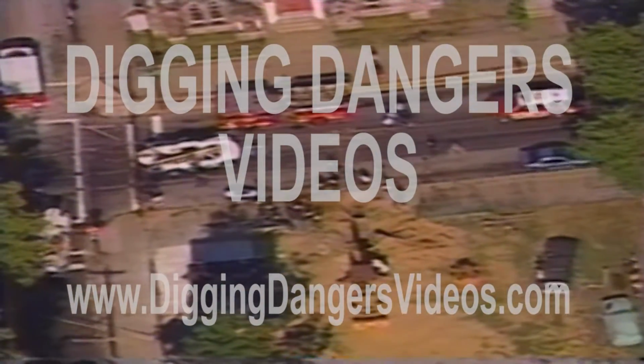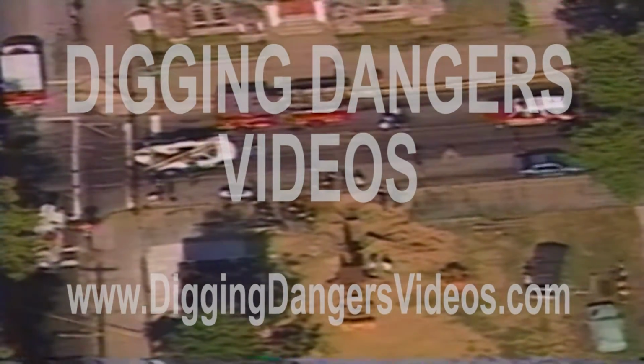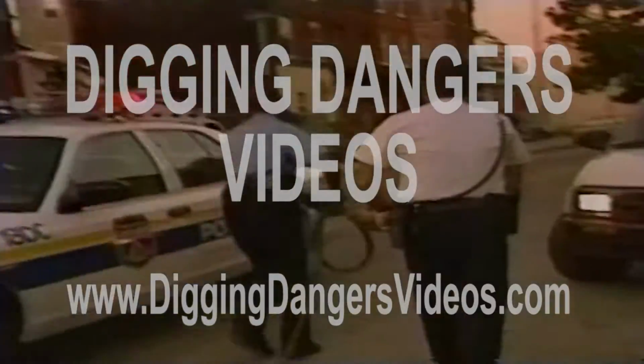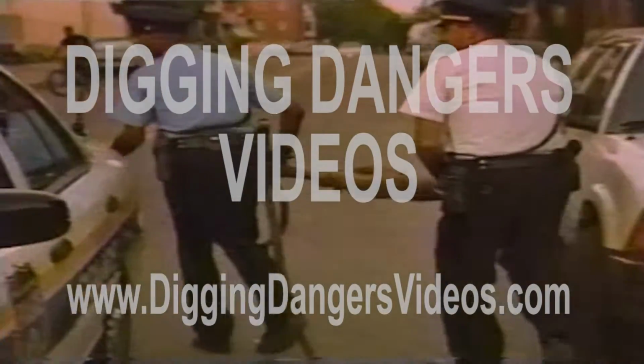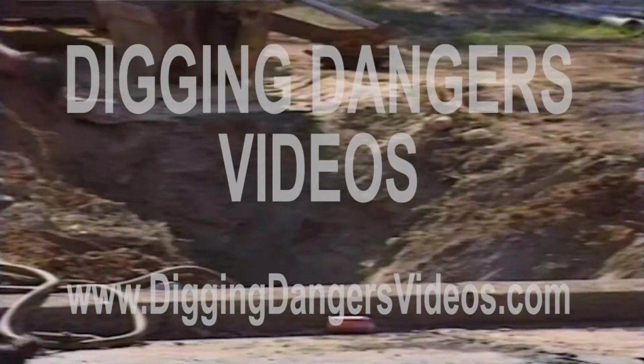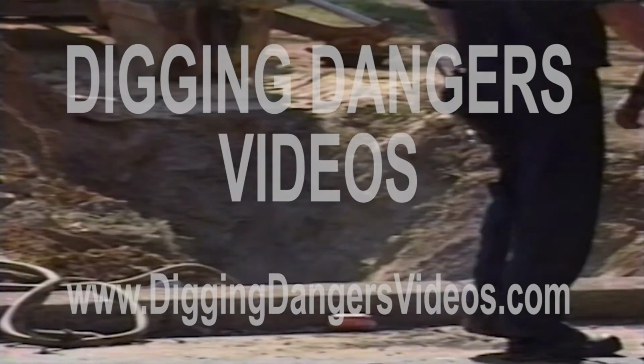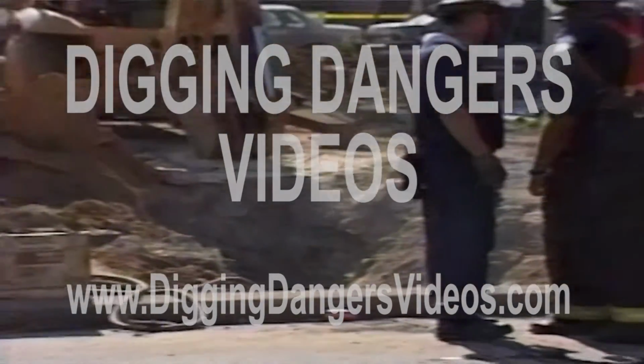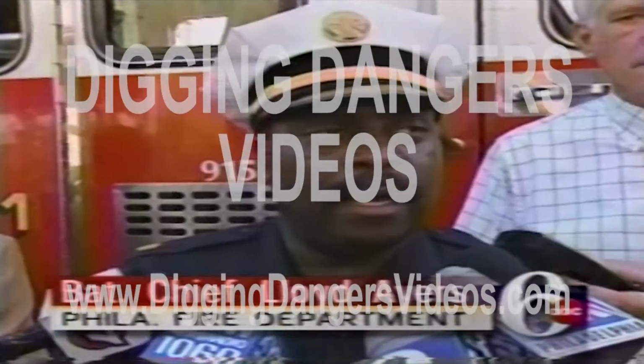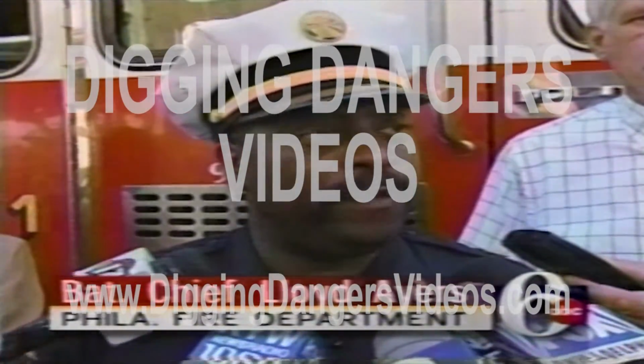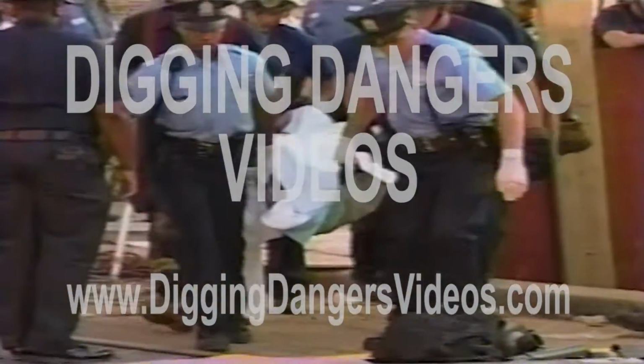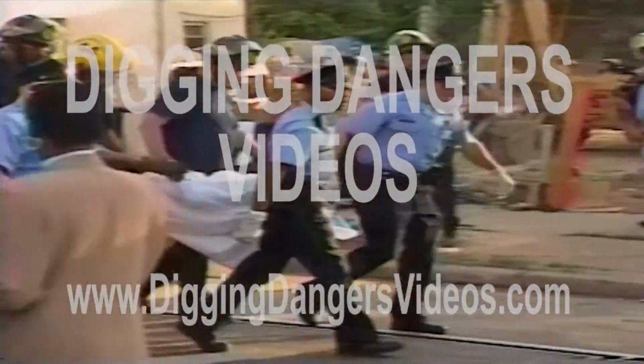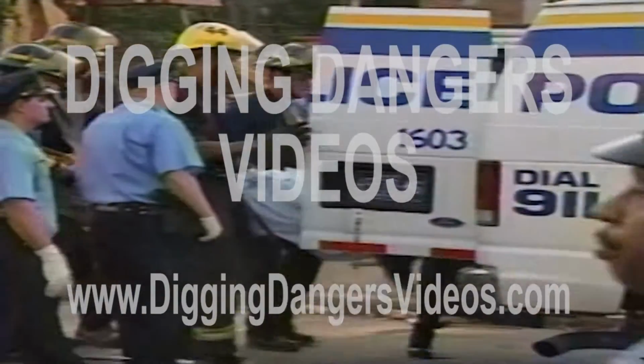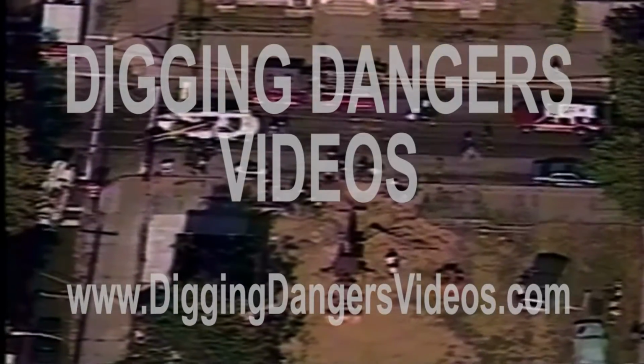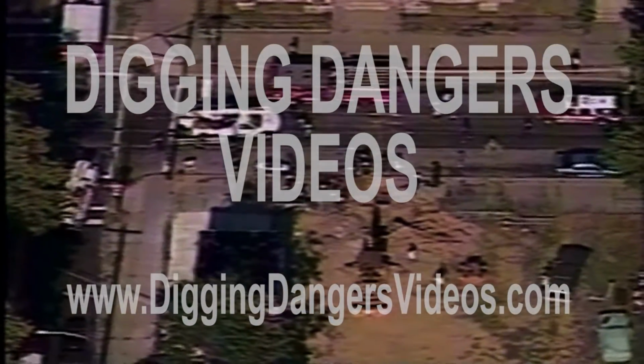Two men died in this accident. One was working in a trench to install a sewer line to a new business. He was using a jackhammer to break up a piece of concrete partially buried in the bottom of the trench. Unfortunately, it was the top of a cable conduit. They came in contact with a high voltage line of one of the underground feeders, which is 13,200 volts. He struck a power cable and was electrocuted. His boss jumped into the trench to pull him out and was also electrocuted. A third worker also tried to help and suffered serious burns.